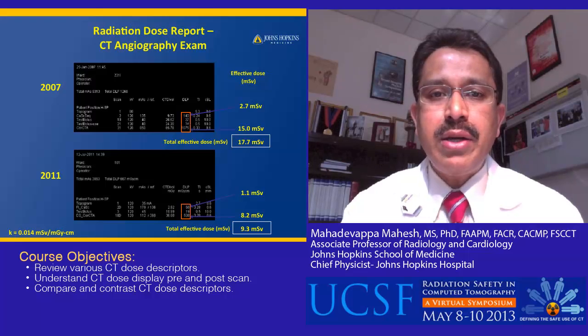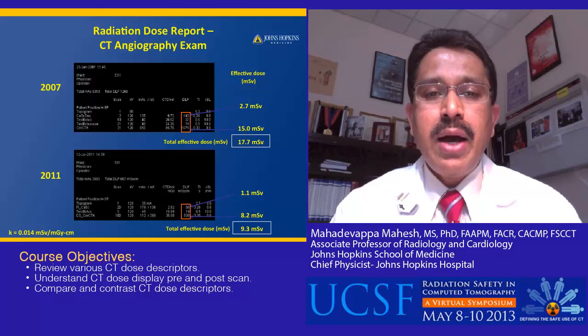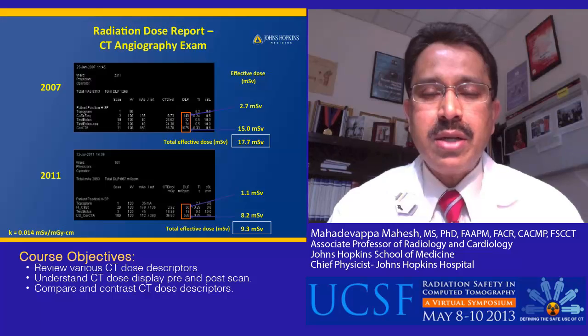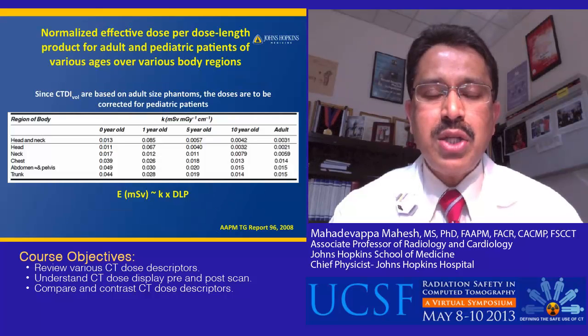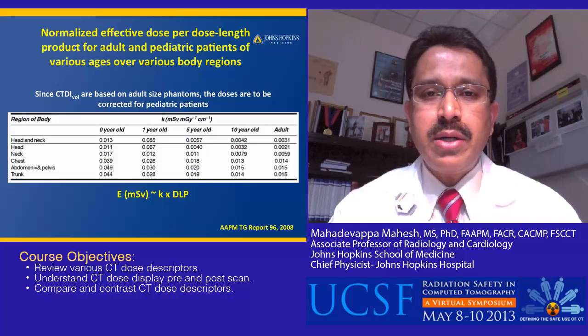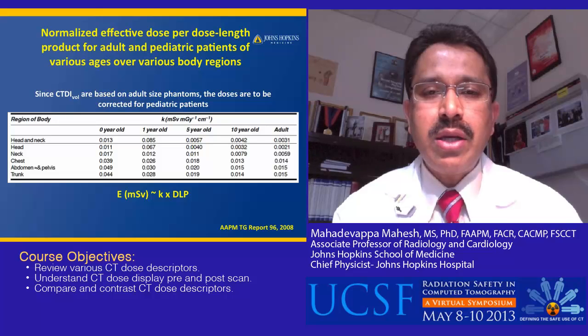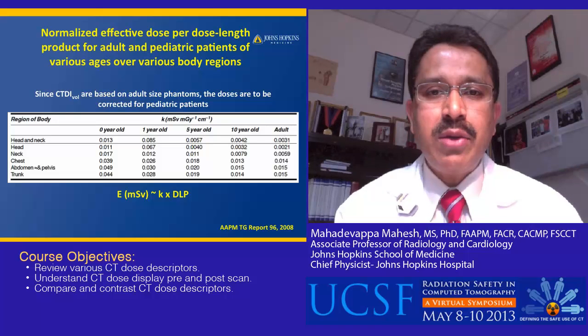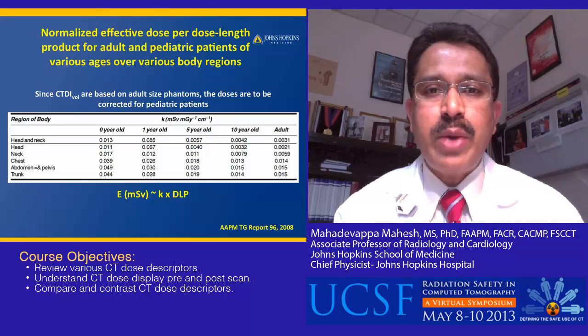Shown here is a rough idea of how the available dose information can be used for calculating effective dose for comparison purposes. The CT dose displays on the scanner are based on the standard 32-centimeter phantom for the body and the 16-centimeter phantom for the head, and the same is done for pediatric protocols. However, for a pediatric patient, the displayed values must be corrected to accommodate for size variation. This can be done using a table where conversion factors established for adult size are corrected for different age groups, allowing the displayed DLP to be used to arrive at effective dose values for a particular CT protocol.